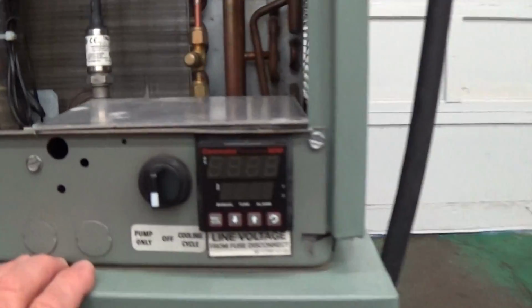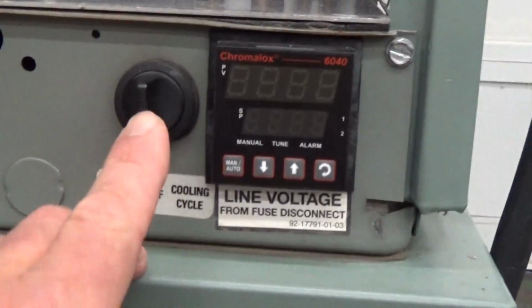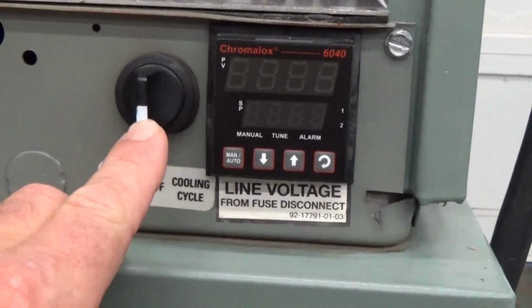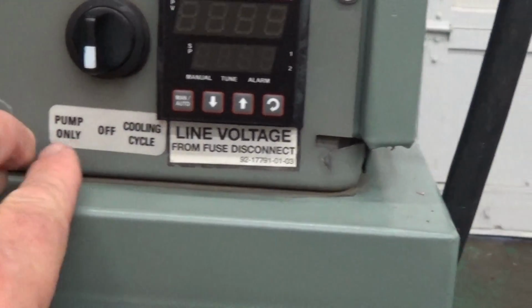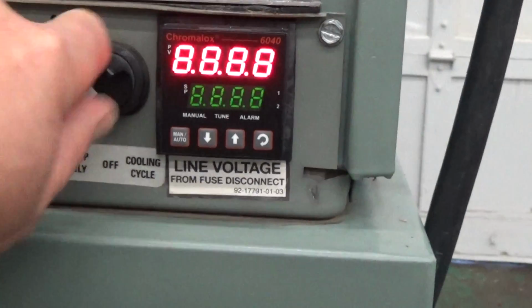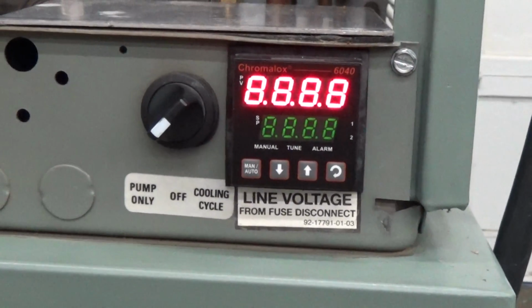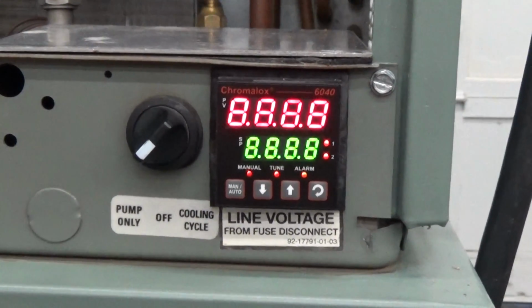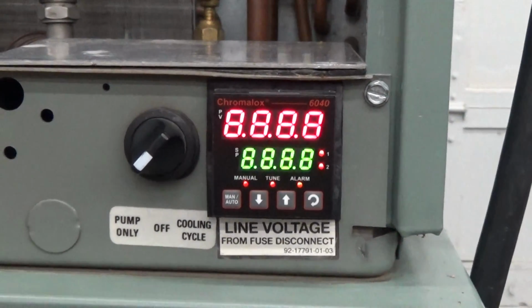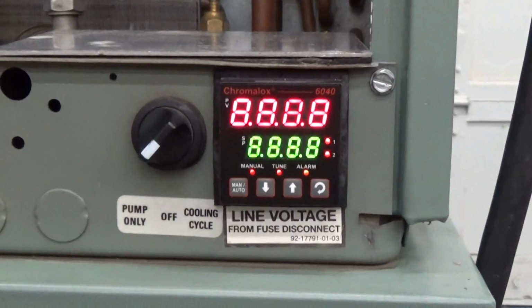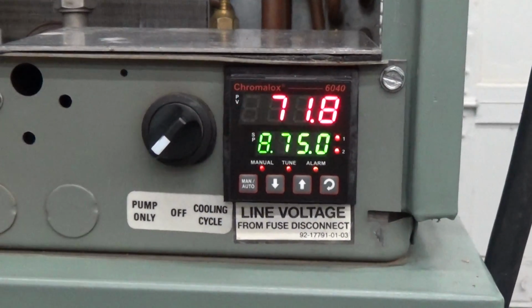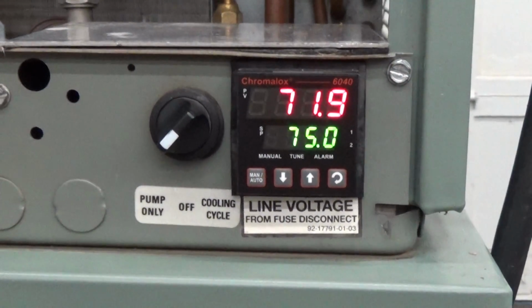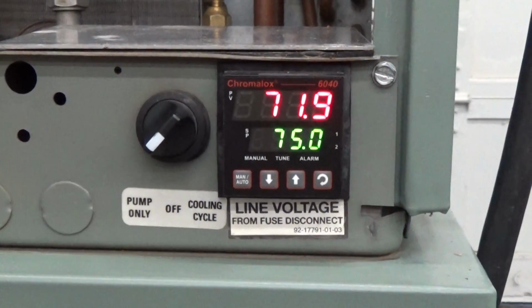There's basically a simple selector switch here. You have off mode, the white little tab points to off, then cooling cycle and pump only. When you turn on pump only, just the pump runs. When you turn on off, everything is off. And then cooling cycle, the pump is also always on. But you're only going to start cooling based on your set point and so forth.